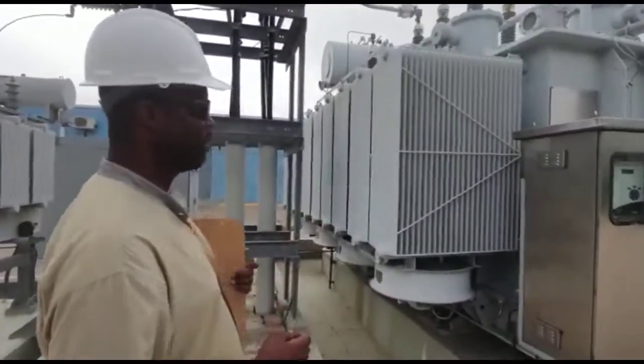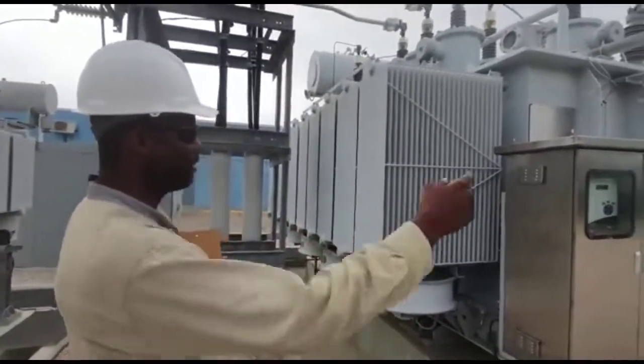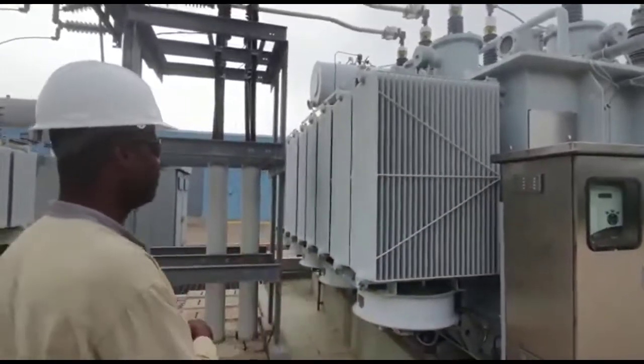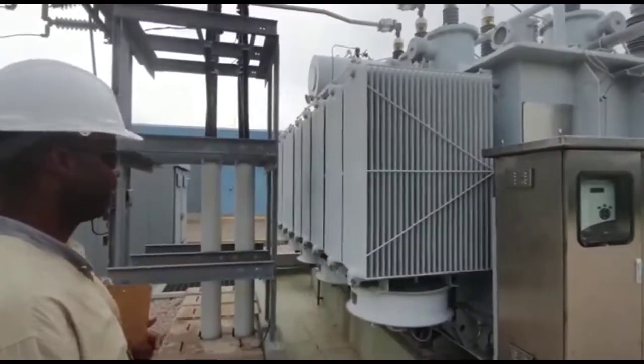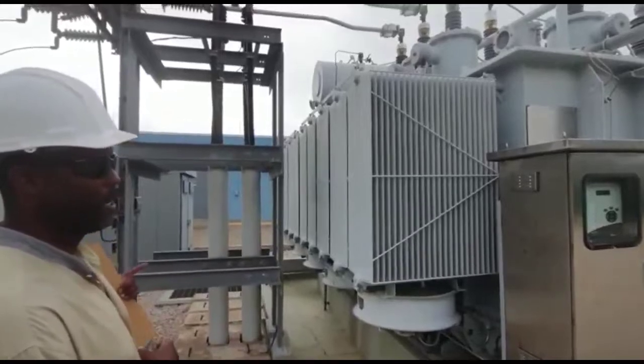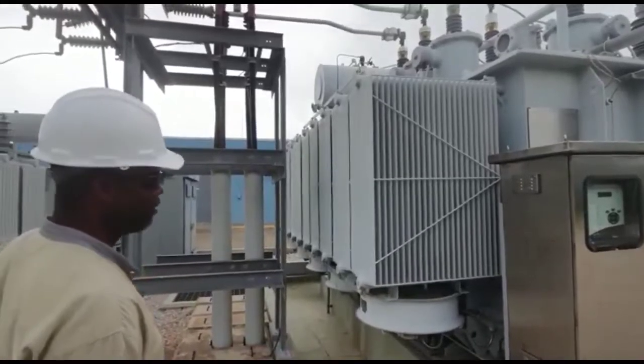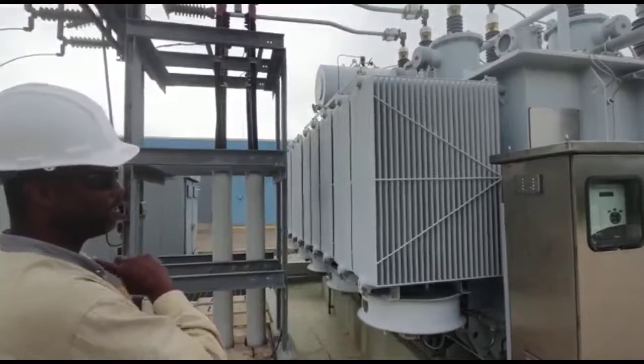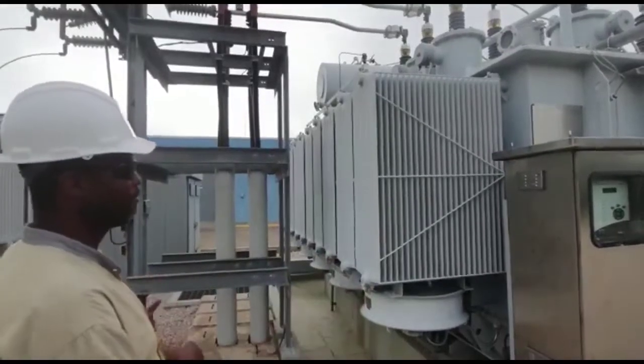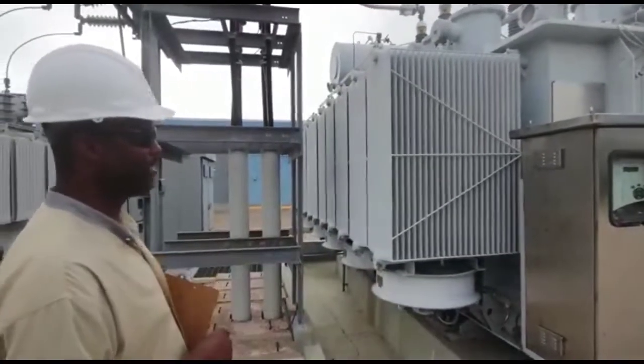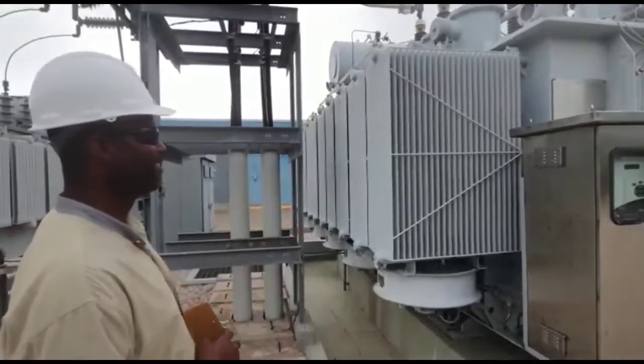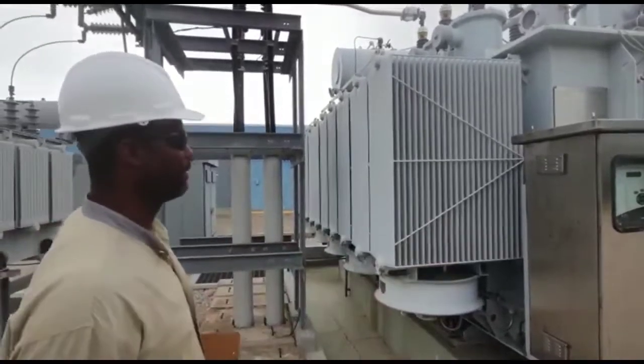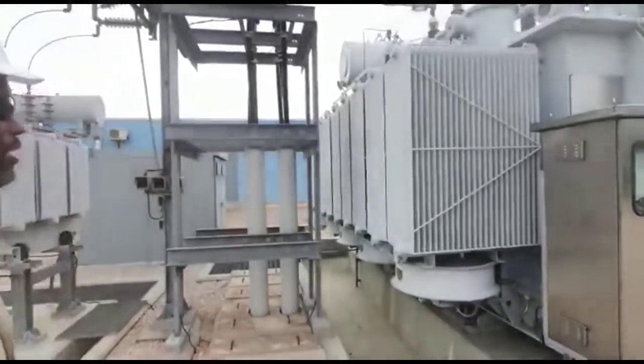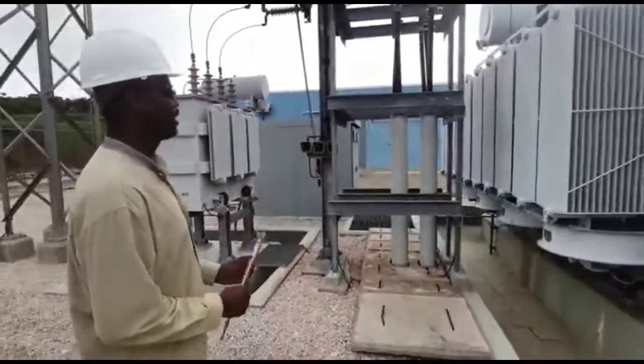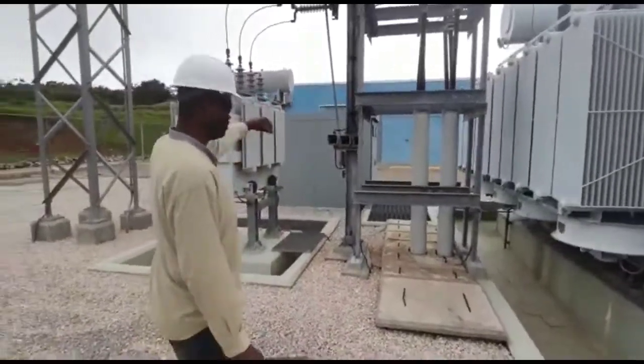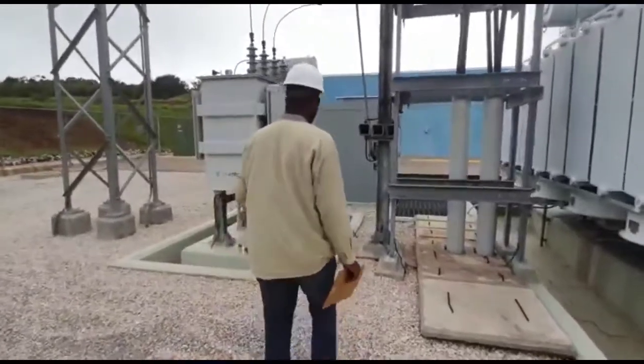So how this transformer works, 69 kV comes in and it is stepped down to 34.5 kV to go to the wind turbines. But when the power is flowing in the opposite direction, that 34.5 kV is stepped up to 69 kV and it flows to JPS, where it goes into the national grid. So we're going to go back around there now and we'll look at the side that has the tap changer.